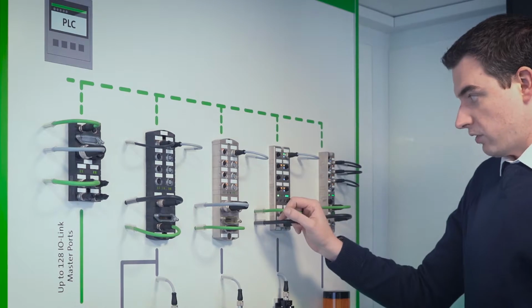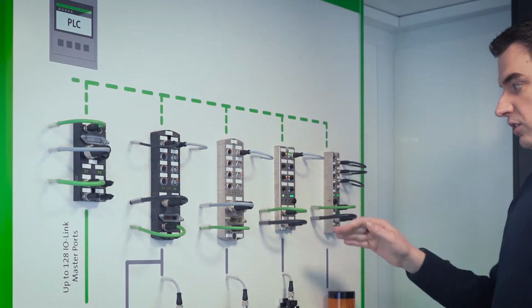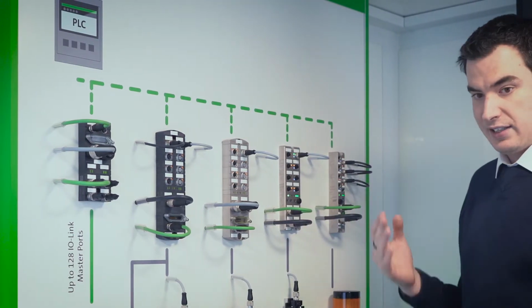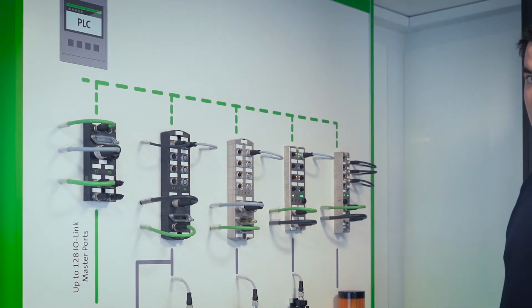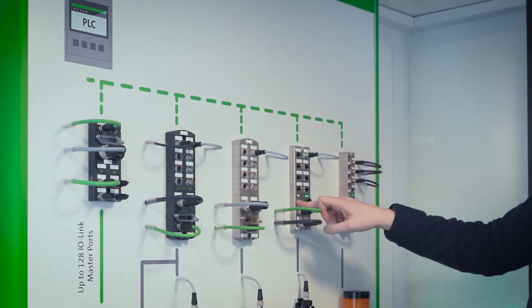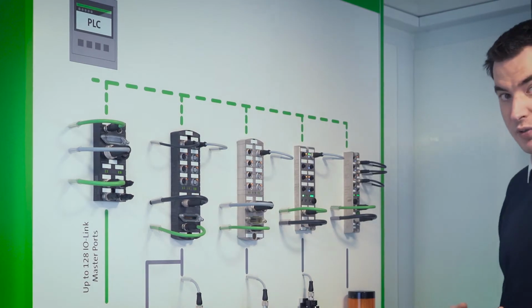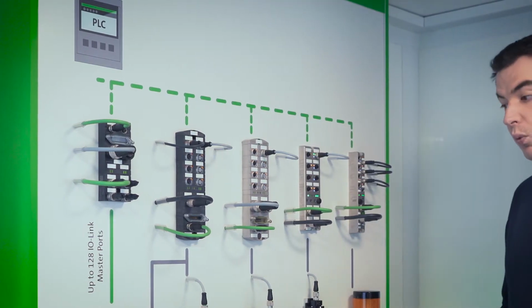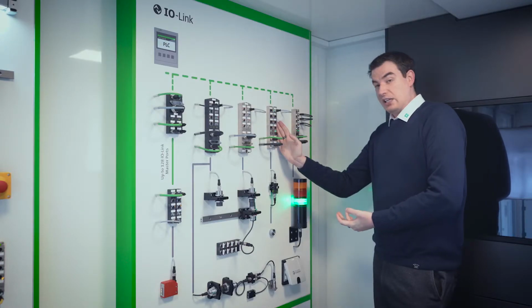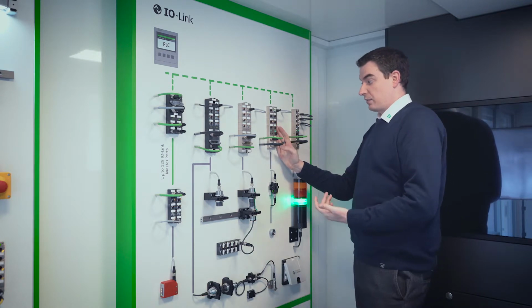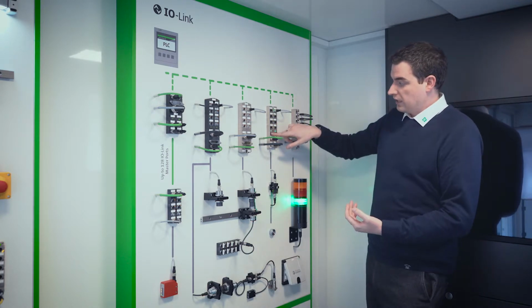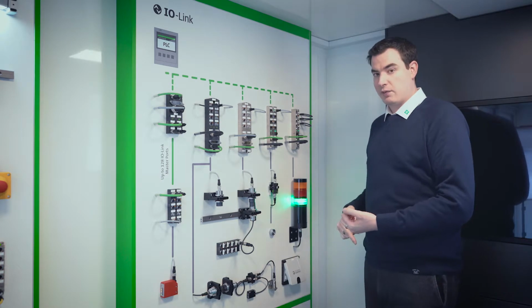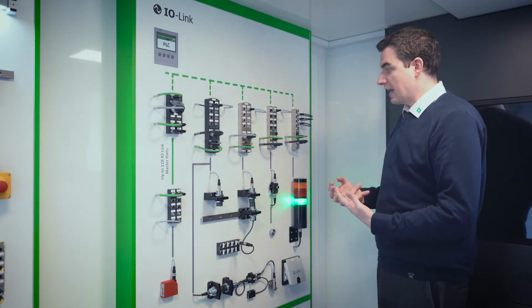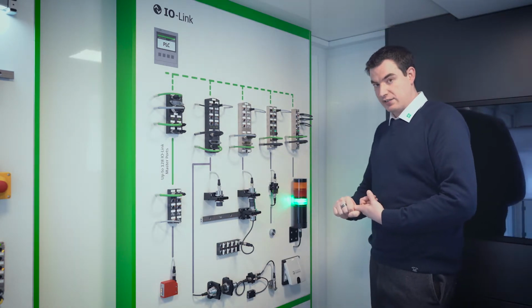We do have another range called Solid 67. Huge benefit of the Solid 67 is that it has Ethernet IP and Profinet chips within it, so that using the rotary switch on the front you can change communication protocol as needed.